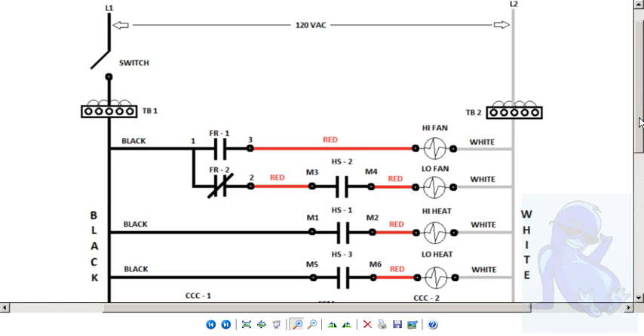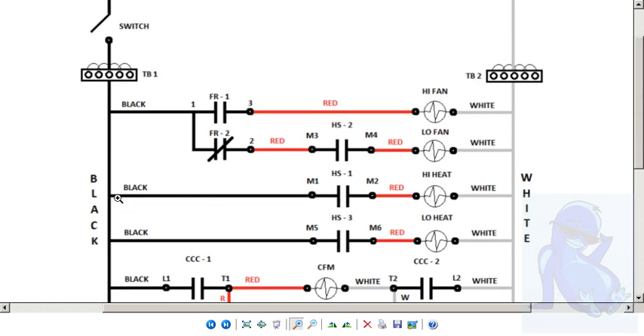Also on this ladder diagram we have M1 to M2, and this is the sequencer, and this here is our high stage heat. When it calls for the high stage heat, it's going to kick on, and here is our low stage heat. This will probably connect first, and then this one will connect next. This doesn't have to be a sequencer. It could be a solid state device, a little circuit board.